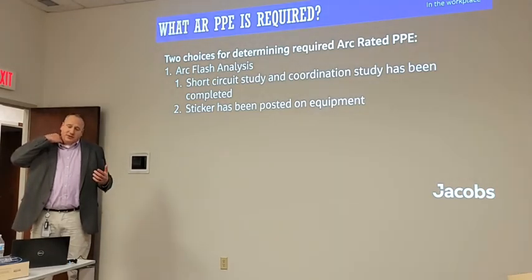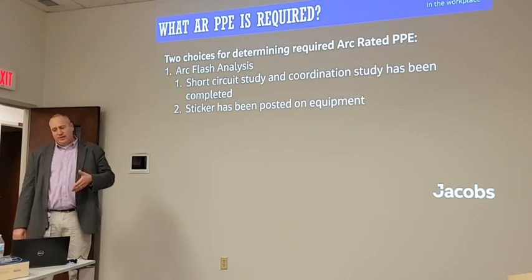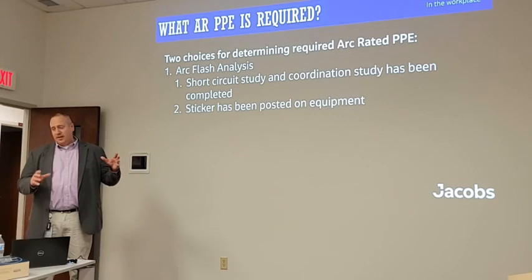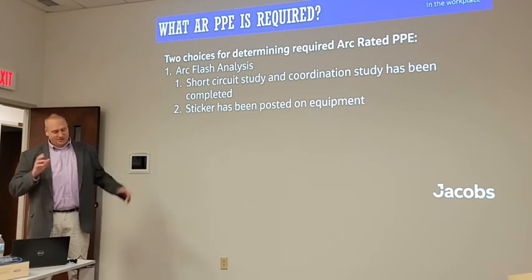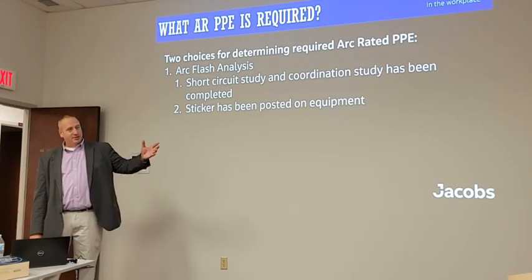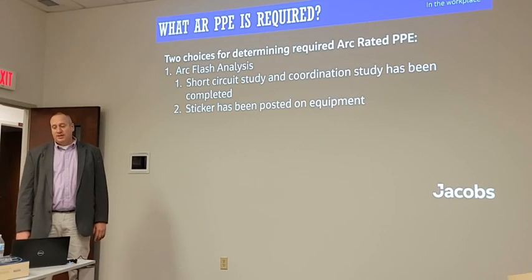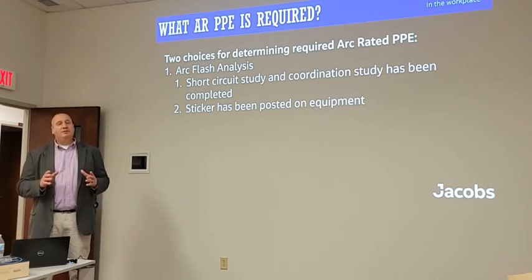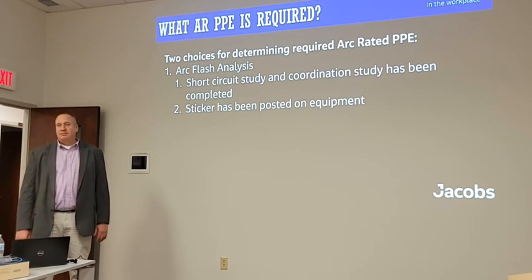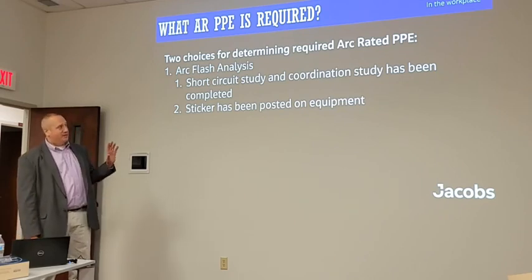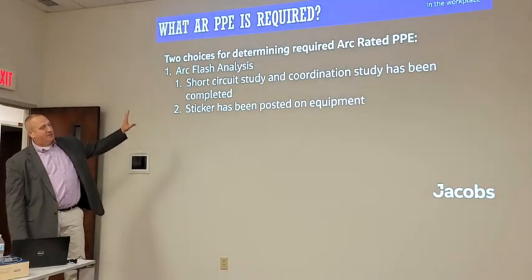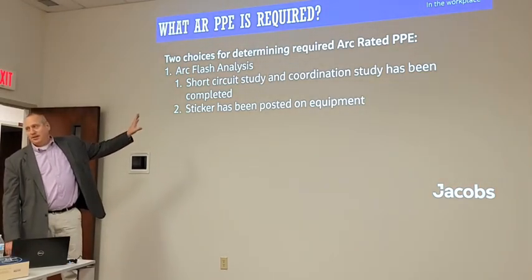I've had scenarios where we've done the analysis on the equipment, and then not too long after that, downstream of some Schweitzer relays that gather all the information that a nerdy power engineer would really love to see, with the vectors and everything that you'd ever want to dig into, was upstream. We had an arc flash event, and you're able to go download the event summary from the Schweitzer relay, and that reassured me that the teams that put together these IEEE standards to do the equations for the analysis are smart individuals, and the calculations are good.